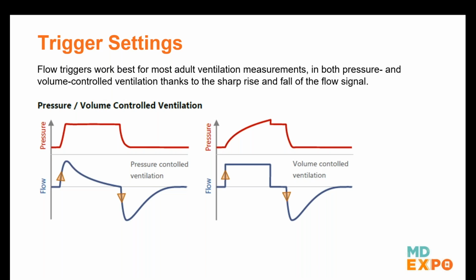The reason is that in most applications you will have your gas flow analyzer, ventilator on one side and test lung on the other side. Then you will have a positive and a negative flow through the gas flow analyzer. Usually you are either in pressure controlled ventilation, maybe you've heard that term, or in volume controlled ventilation on a ventilator. In both cases, we can see typical waveforms here, pressure controlled and volume controlled. Most important is that in both cases we have flow signals that have very steep rising and falling edges. So we can easily use the flow signal as a trigger signal for most of our applications.